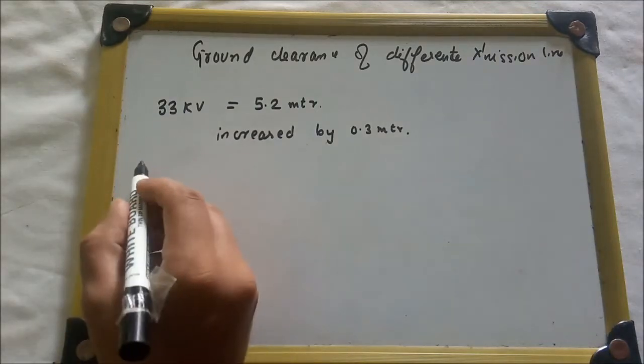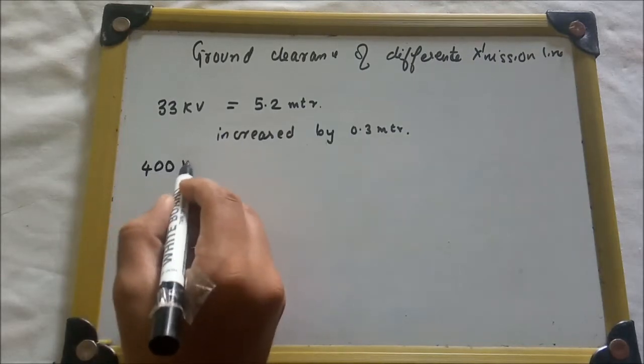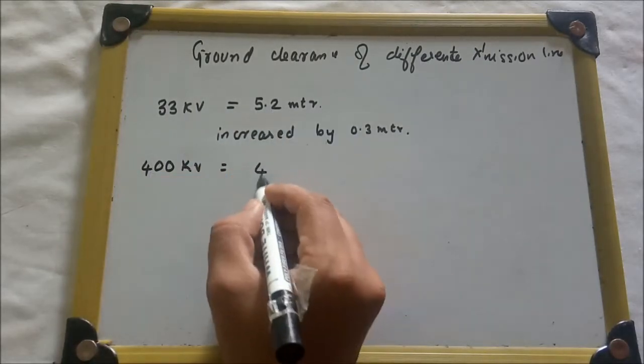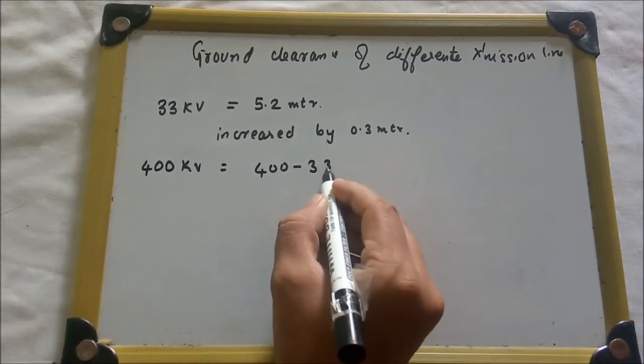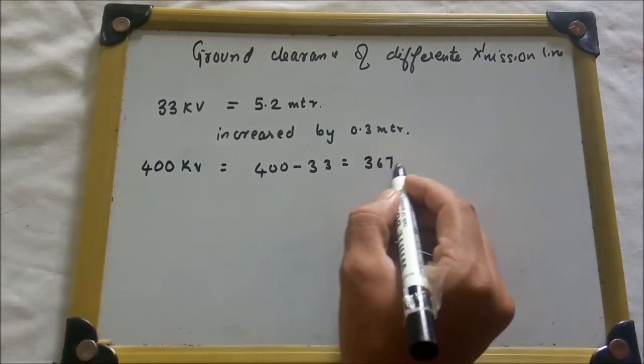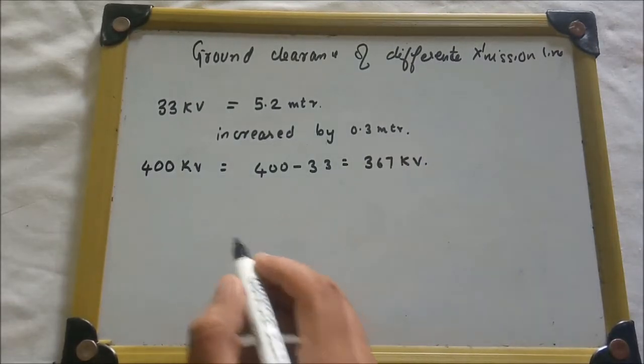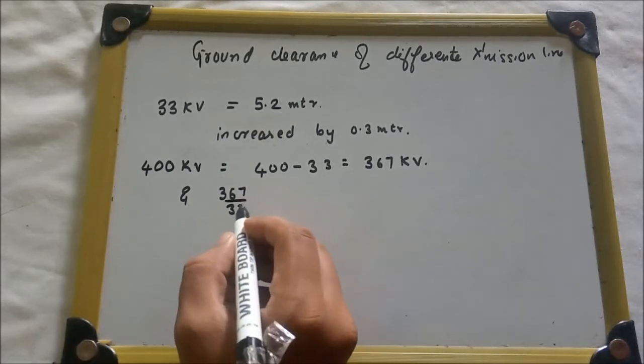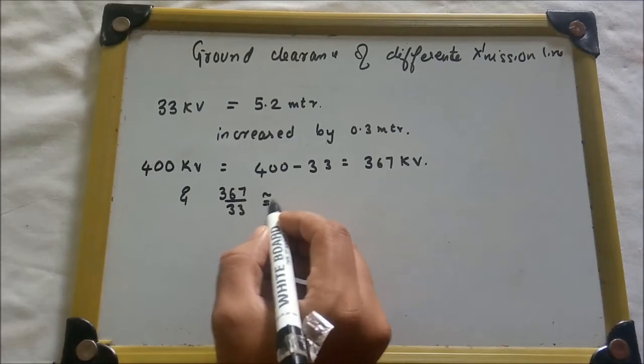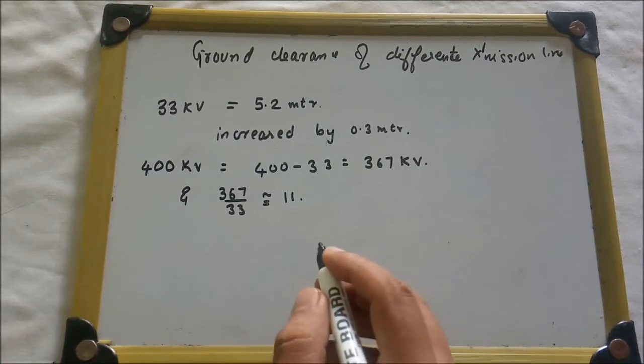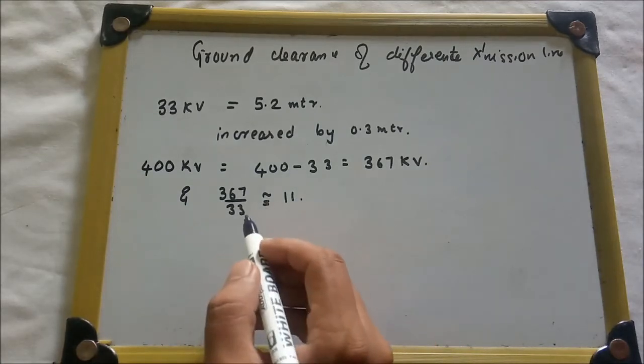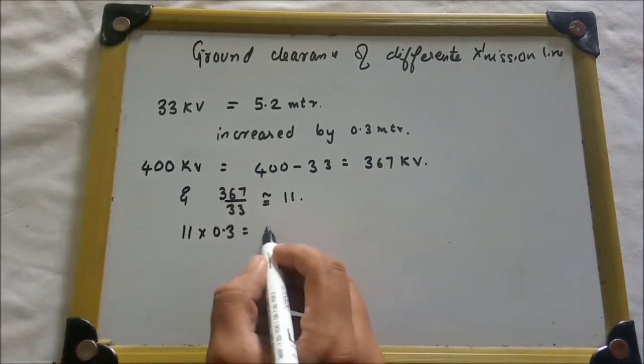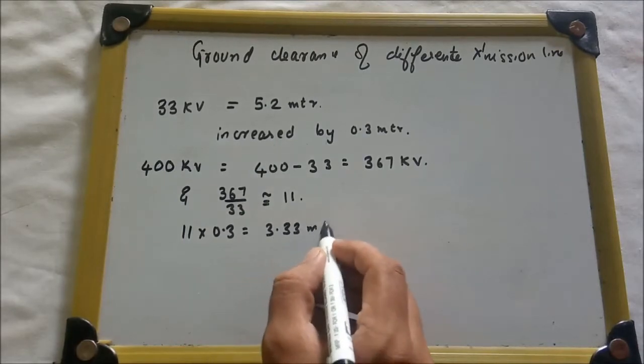What will be the minimum ground clearance of a 400 kV line? First, the base is 5.2 meters for 33 kV. We subtract: 400 minus 33 equals 367 kV. Then 367 divided by 33 gives us approximately 11.